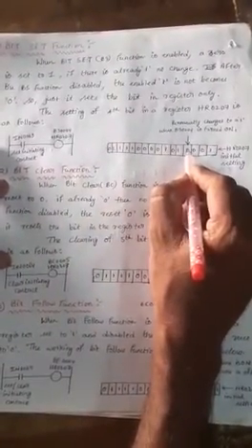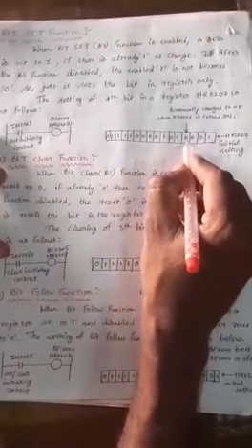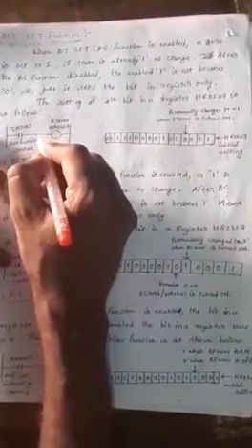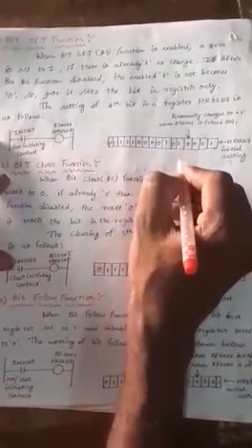That means, for example, in this register we consider the fourth bit, and the fourth bit is 0. By using the bit set function, we can make that fourth bit, that is 0, as 1 by enabling the bit set function. And if you disable the bit set function by opening the IN0063 contact, then that enabled 1 status is not changed, it remains as 1. Similarly, if you apply the bit set function to a 1, even though we enable the bit set function, it does not make that 1 as 0, it remains 1. So that is about the bit set function.